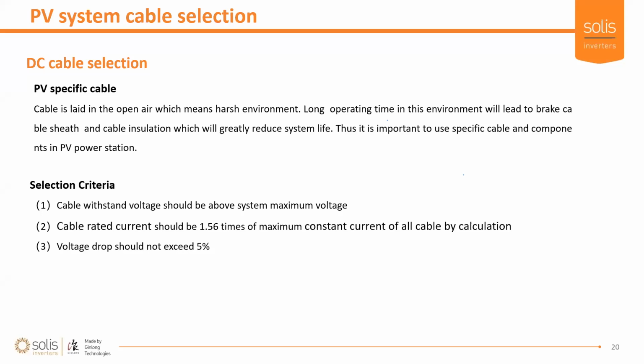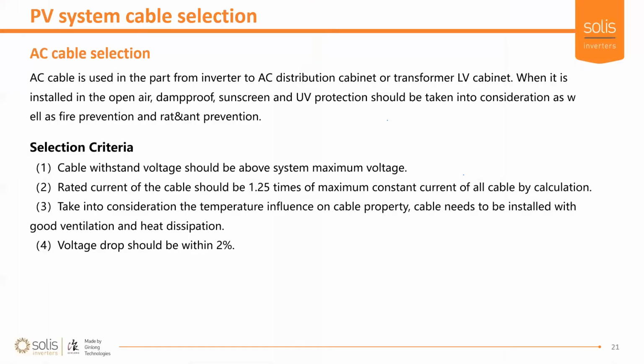And finally, you need to consider the voltage drop. The inverter doesn't really get influenced that much by the voltage drop on the DC side. However, you will come into efficiency problems if you don't consider it. We're more concerned with the AC side voltage drop, which is what we're going to talk about now. The AC cable, we're only talking about the AC cable between the inverter and the mains incoming grid connection into the installation. Again, we have to consider the design specifications.